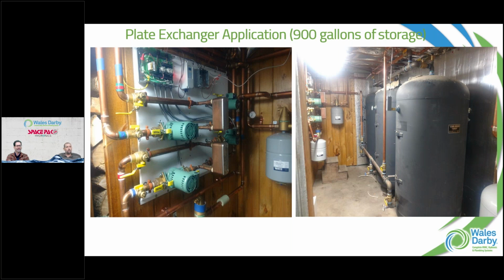So this guy was storing 900 gallons of BTUs, basically. Depending on which zones are calling, whether small or whatever, they're just feeding off those 900 gallons. If we deplete it enough, eventually it'll turn on an outdoor unit to make it up. But here we look at dollars and cents and utility rates to see when it makes sense. That was definitely a cool one.